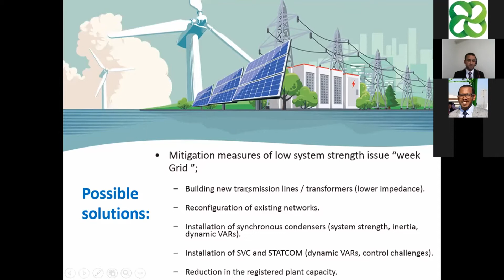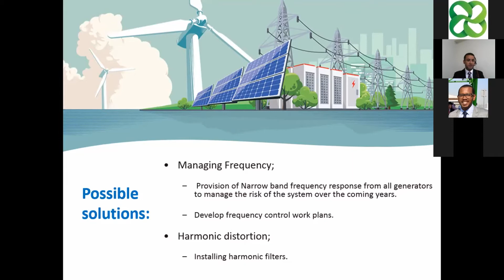A possible solution to managing frequency is to come up with a narrowed dead band for the frequency, so we make the frequency response from all generators quicker and manage the risk of the system over the coming years. We can also develop frequency control work plans to make it more efficient. The possible solution for harmonic distortion is, of course, installing harmonic filters.